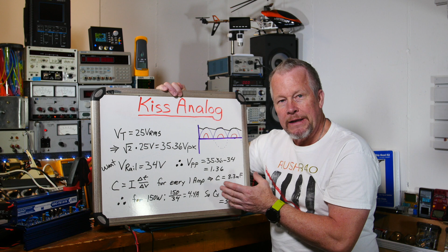So change of voltage, if you say it's 1 volt peak to peak, and you start with say 1 amp, then those things go away and you end up with change of time, your discharge time. And I was saying, well, here in the US, 8.3 milliseconds is half a cycle. So if we're discharging half cycle, charging half cycle, that was just a rough place to start. Well, if you do that, you're going to be pretty conservative, because capacitors could have a 20% tolerance, plus temperature and aging and stuff, so it's good to be somewhat conservative.